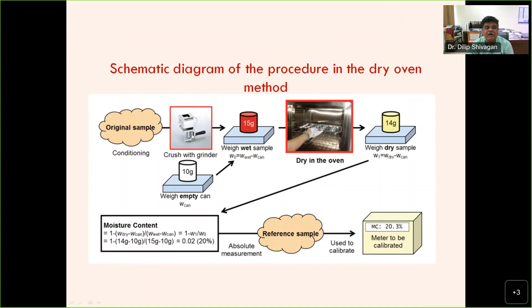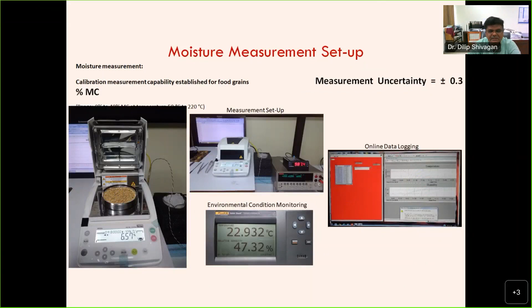At higher moisture content or at lower moisture content they will break. So it is initial mass minus final mass divided by total mass, so total weight. So it is based on that. So you need to have a very high stable oven or integrated oven like this we have. So we have to remain traceable with temperature as well as mass. The standard has characterized this with mass, and with this we have validated. We have also taken part in an international comparison where the NMI of Korea was the pilot, and we could do wood samples and some food grain samples, and with this we have standardized.